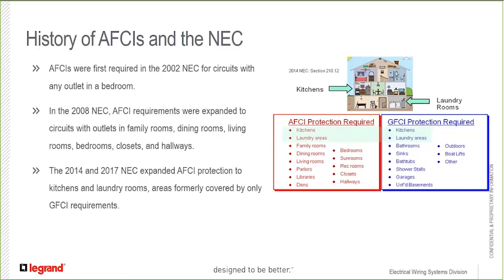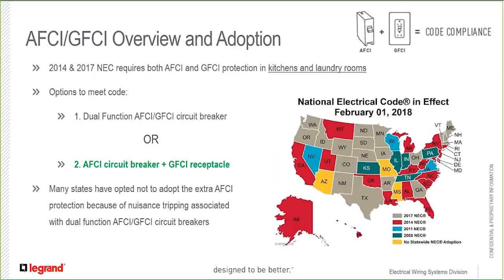So you see at the right here the chart that shows where AFCI protection is required and where GFCI protection is required, and we've pointed out that kitchens and laundry rooms now require both. So to reiterate, the 2014 and 2017 National Electric Code requires both AFCI and GFCI protection in kitchens and laundry rooms. There are two options to meet code. The first is to use a dual function AFCI GFCI circuit breaker. The second option is to use an AFCI circuit breaker paired with a GFCI receptacle.